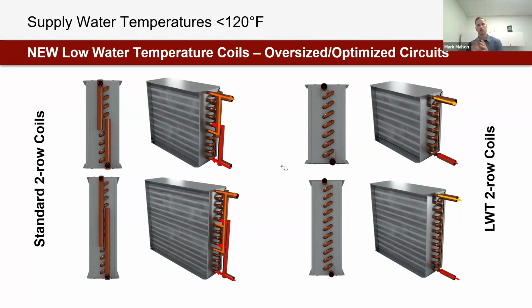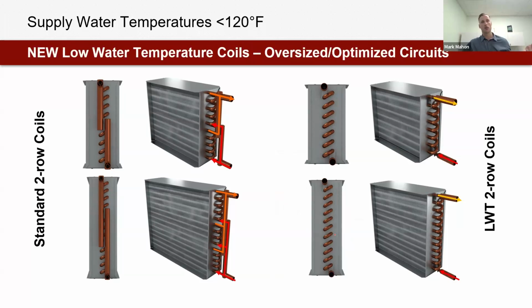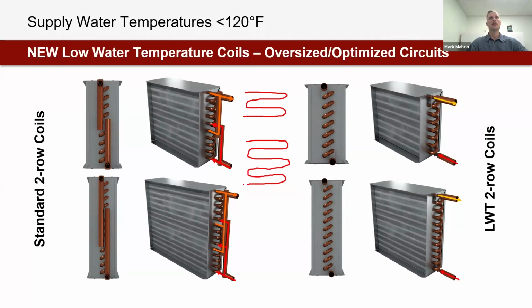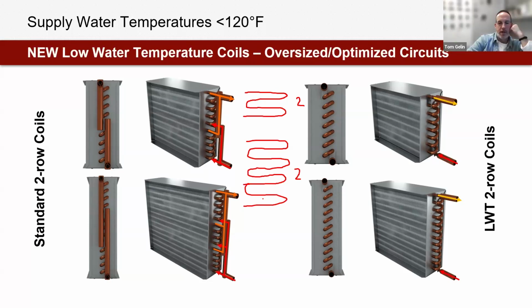Now, what we're seeing with this reality and paradigm instead is we're seeing the total tube length grow. And that's really what we're trying to get as a benefit here. If I have 4 tubes versus if I have 8 tubes, double the tube length, and if I have equal GPM, so the biggest consideration is the same fluid flow rate. If I have 2 GPM traveling through 4 tubes, and if I have 2 GPM traveling through 8 tubes, the 8 tube version is going to have a lot more temperature drawn out of the tube because the fluid's inside of the heat exchanger for longer. So this is the condensing boiler of coils, kind of.